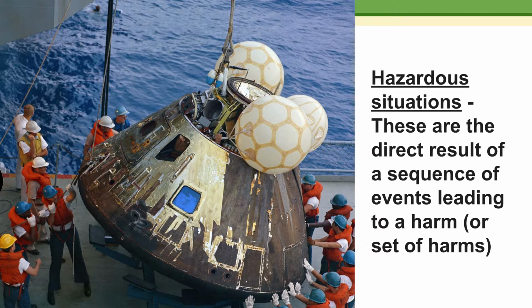So this is the sequence of events that we're going to imagine happening. So the surgical stapler is being used and the glove of the surgeon gets caught. The hazardous situation that could arise from this is if the glove tears, which is part of this foreseeable events, the following hazardous situation could arise. The skin underneath the glove of the surgeon could be exposed, and if it's not properly sterilized or it's no longer aseptic, then the aseptic field of the surgical procedure could get contaminated with bacteria that could cause an infection. And so this is a hazardous situation.